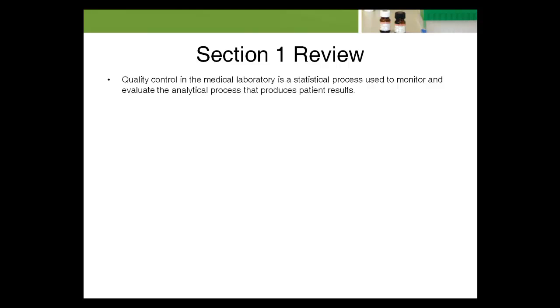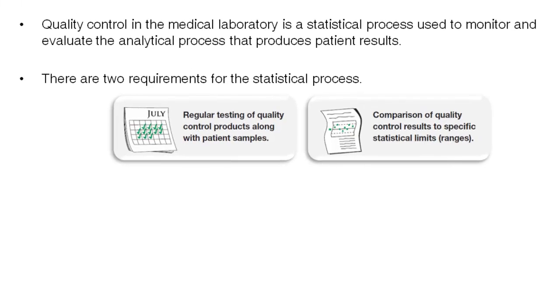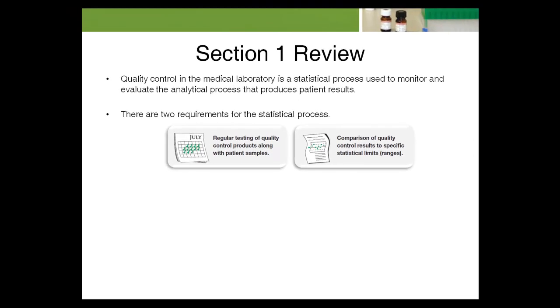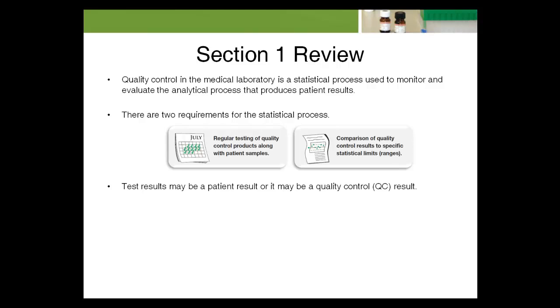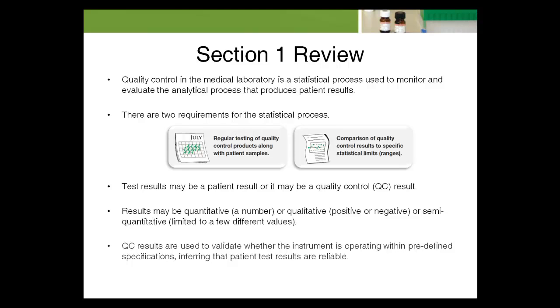We've reached the end of this module. Let's review some basic points. Quality control in the medical laboratory is a statistical process used to monitor and evaluate the analytical process that produces patient results. There are two requirements for the statistical process: regular testing of quality control products along with patient samples, and comparison of quality control results to specific statistical limits. Test results may be a patient result or a quality control (QC) result, and may be quantitative, qualitative (positive or negative), or semi-quantitative. QC results are used to validate whether the instrument is operating within predefined specifications, inferring that patient test results are reliable.